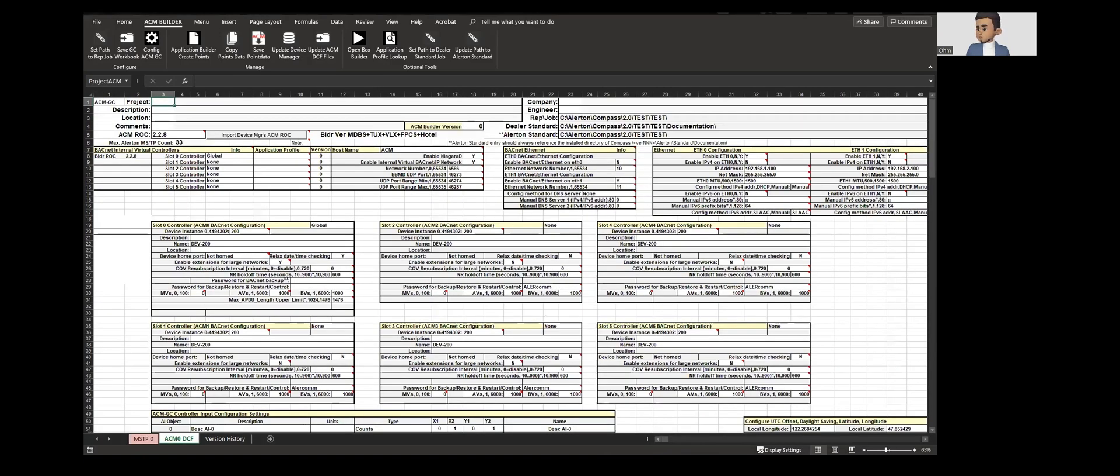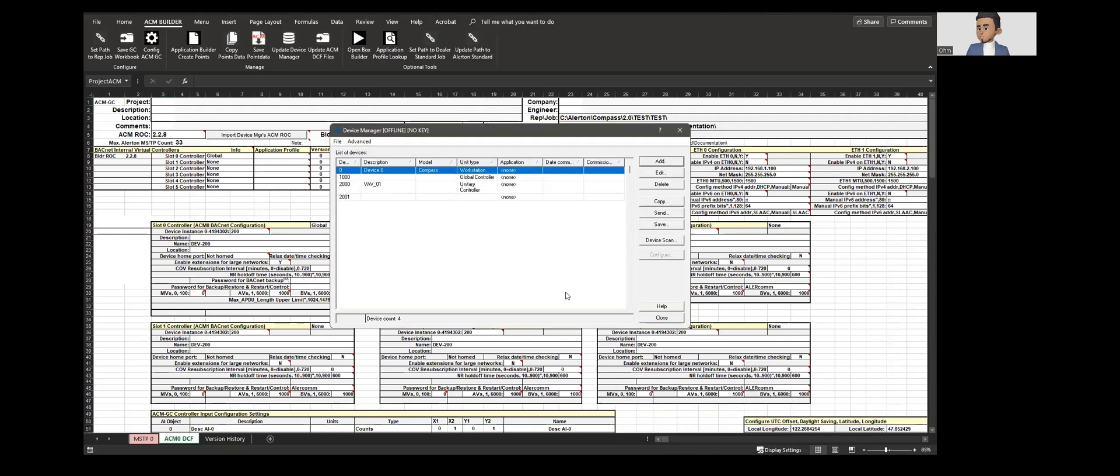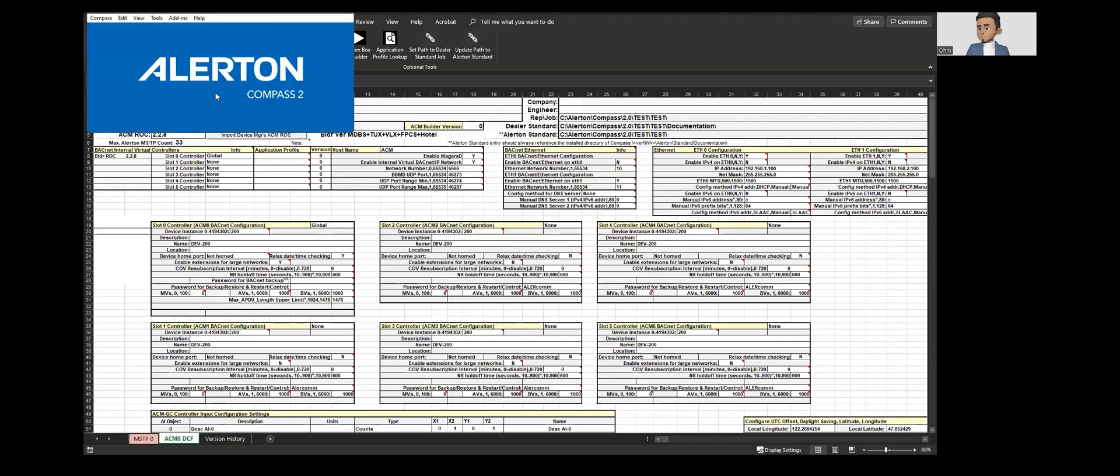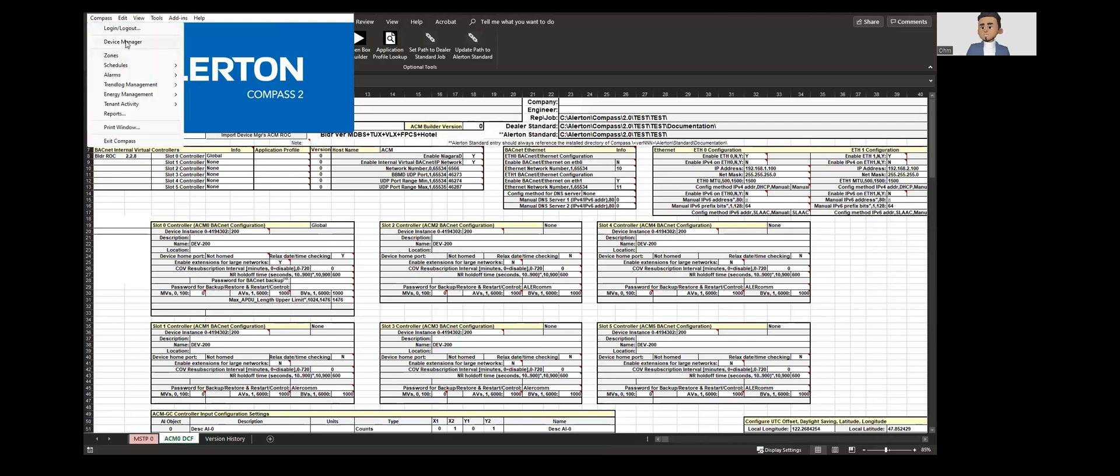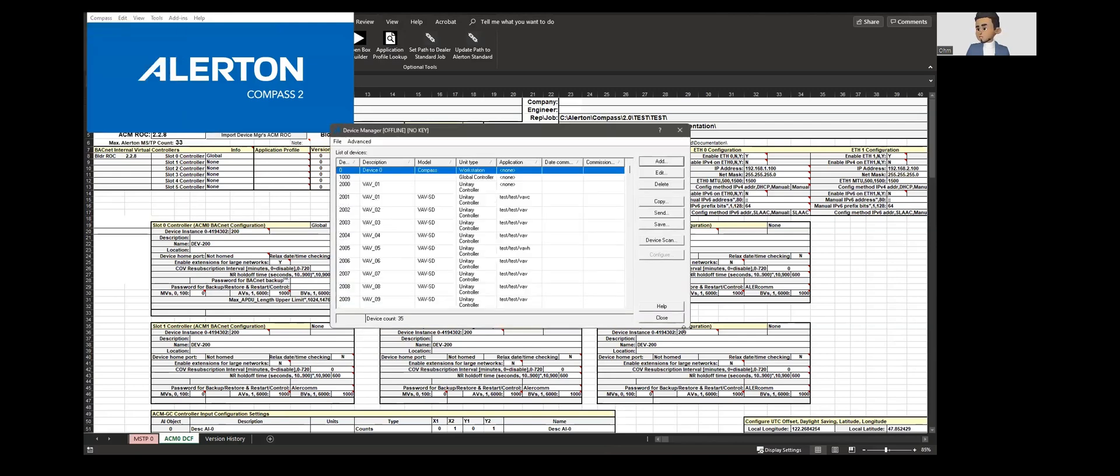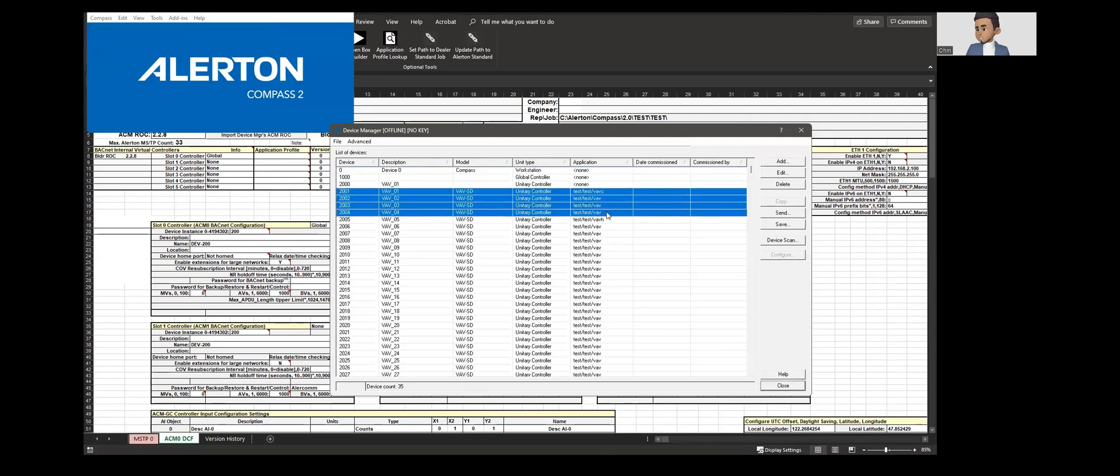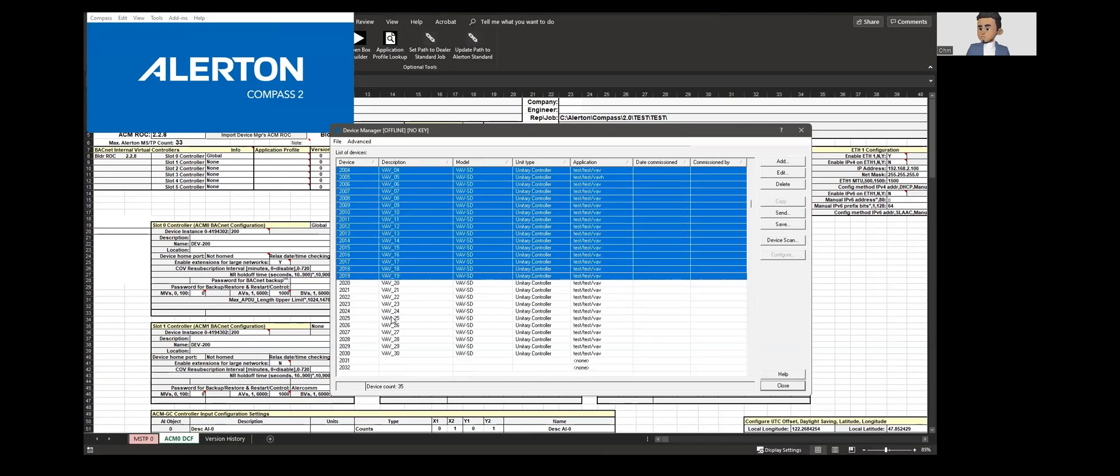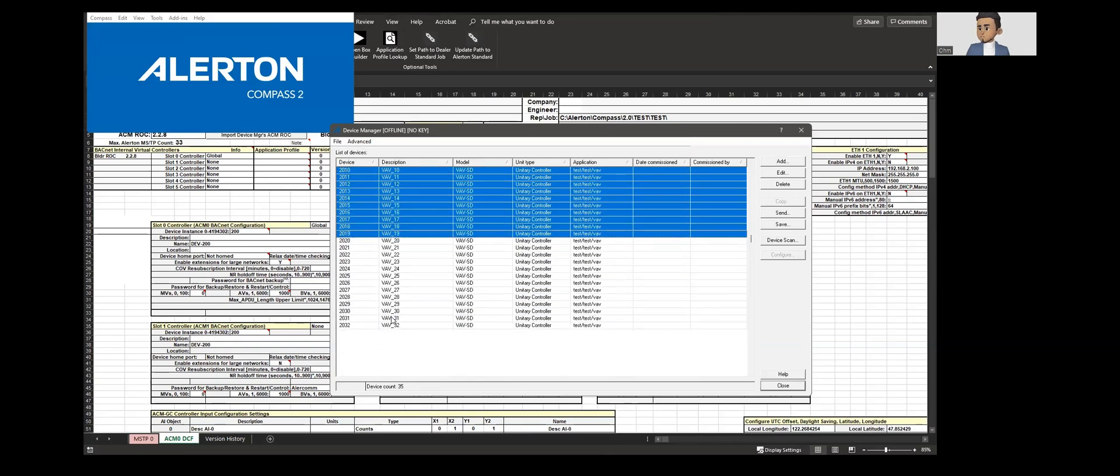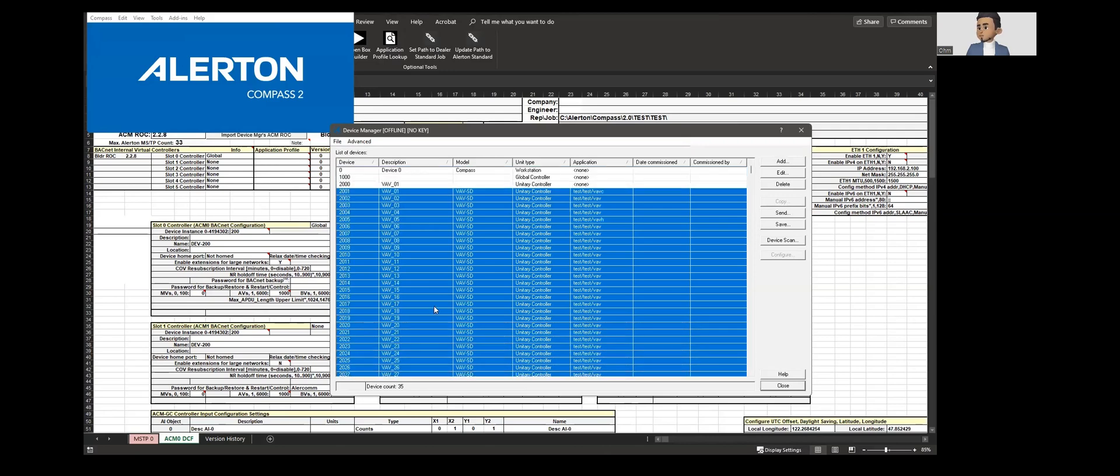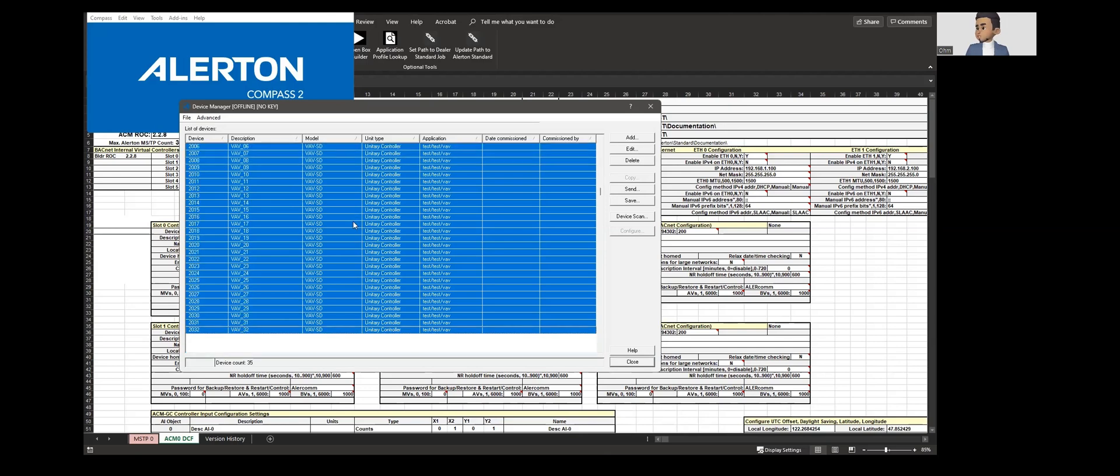Let's go back to Alerton. Let's close this window. Let's go to Compass, go to device manager and we can see that the application is the DDC file which you can see that it is already taken from the spreadsheet and the number of devices that was added to this particular project updated in the device manager.